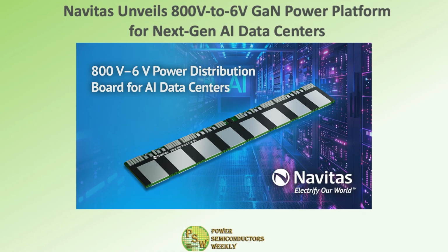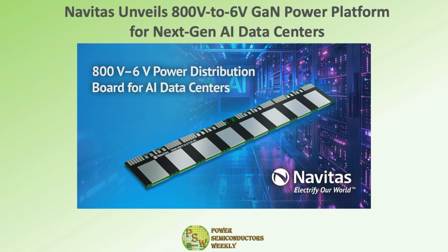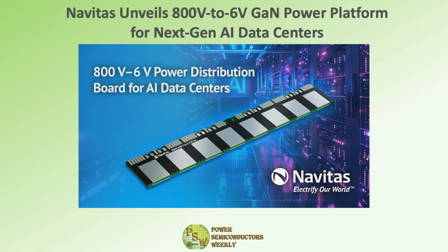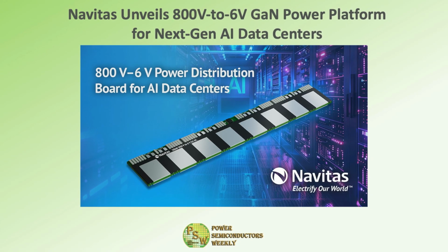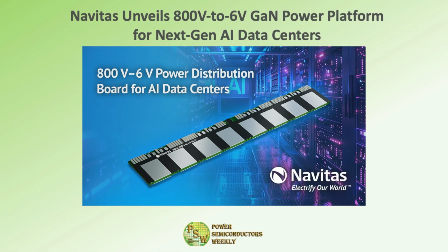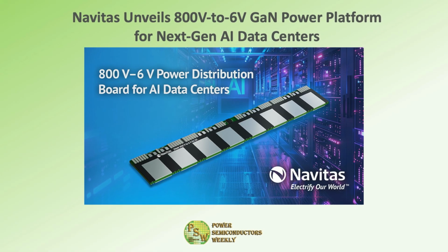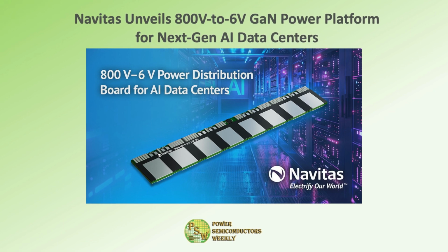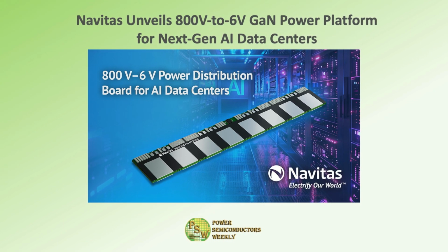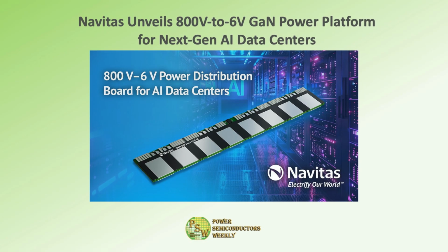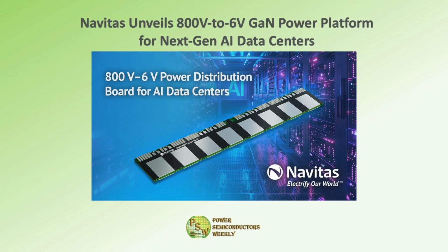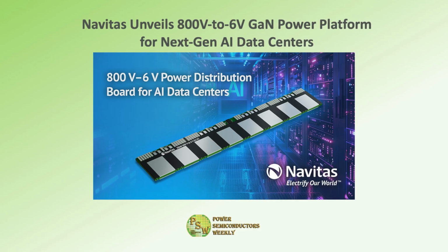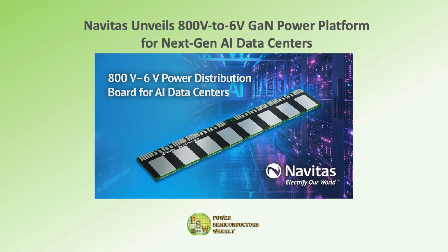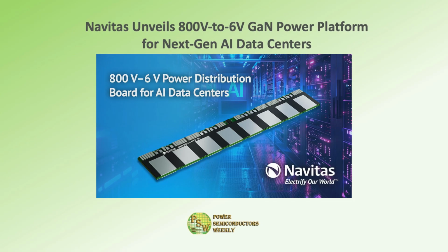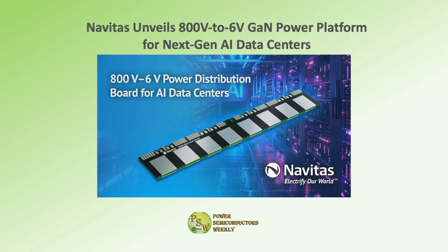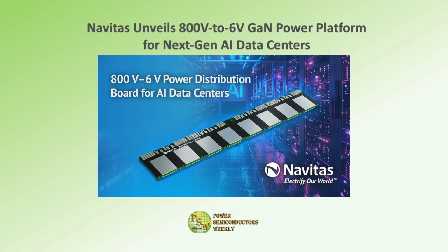Navitas introduced a GaN-fast-based power delivery board that converts 800-volt directly to 6-volt in a single stage, eliminating the traditional 48-volt intermediate bus. Designed for next-generation AI data centers aligned with NVIDIA infrastructure, the board targets 96.5% peak efficiency at 1 MHz and roughly 2.1 kW per cubic inch power density, with an ultra-low profile form factor for close GPU placement. It uses a stacked full bridge with 650-volt GaN and a 25-volt MOSFET secondary to simplify the power chain and reduce losses.